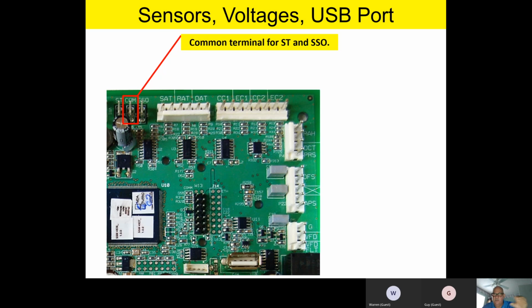And then when you do that, you'll go to thermostat only, no, and then it'll start looking at that space temperature sensor to drive the temperatures in the space. Isn't that the coolest thing? So I like putting a space temperature sensor in a space for 2 reasons. One, it gets rid of the little red light, but also if you have an emergency situation, the thermostat goes bad, you know, you got some broken wires behind the wall, whatever the scenario is, you can actually go to our champion piece of equipment with a space temperature sensor in the space, and you can program that board to maintain any particular cooling or heating set points that you want.